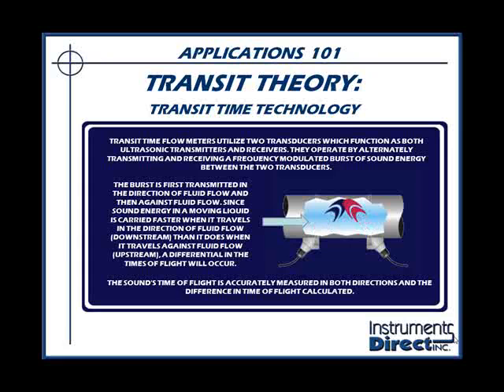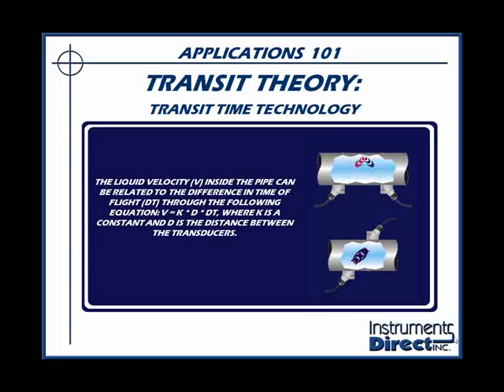So this differential is what we call the transit time theory, or the differential of these times is how they calculate the flow rate on a clamp-on ultrasonic transit time flow meter. And the installation is a variety. In the lower right-hand corner is very similar to the man in the rowboat theory, where this is called a single path or a Z configuration, traditionally used in larger or difficult pipe applications, where we send our sound beam back and forth across the pipe. And the upper right-hand corner is another picture of the dual path or V configuration, which is traditionally used for smaller pipe size applications.